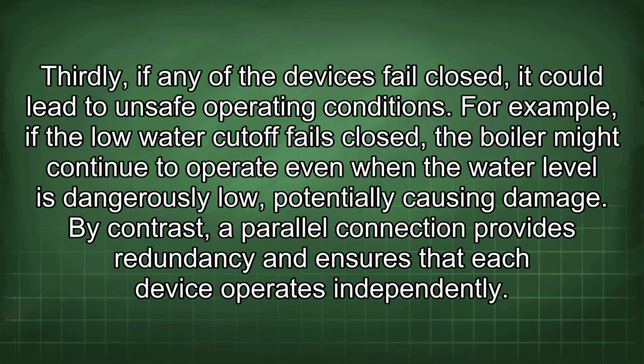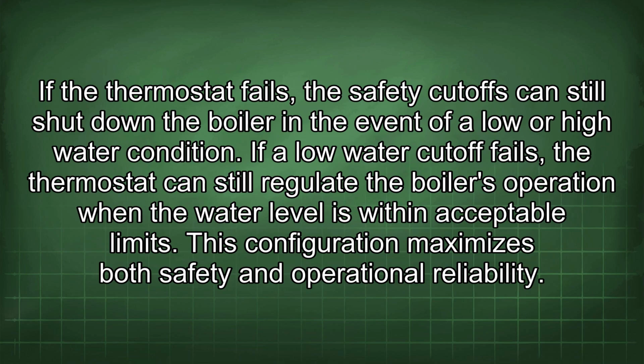By contrast, a parallel connection provides redundancy and ensures that each device operates independently. If the thermostat fails, the safety cutoffs can still shut down the boiler in the event of a low or high water condition. If a low water cutoff fails, the thermostat can still regulate the boiler's operation when the water level is within acceptable limits. This configuration maximizes both safety and operational reliability.